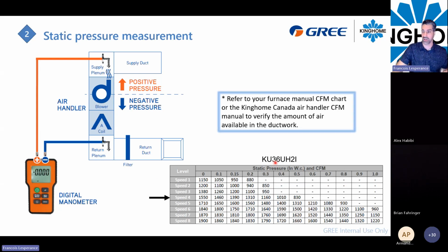So for example, here we have a 3-ton unit, and if I go with 400 CFM, my maximum CFM will be 1200. This is for an air handler, but you can do it as well for a furnace. You can change the speed of the blower on your furnace. So we need to be somewhere between 1050 and 1200. By having 0.3 right here, that's my maximum CFM I can have with a 3-ton unit. If I do my measurement and I have more than that, so my speed is at 4 and my static pressure is 0.2, I know I'm a little bit higher than recommended.